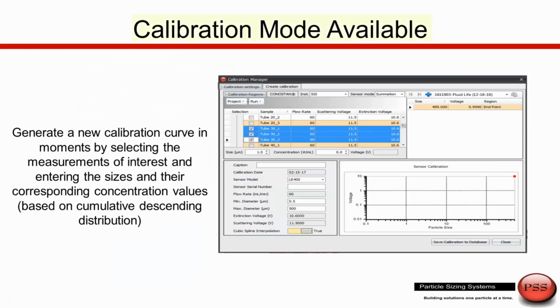Other useful functions in the software include a calibration mode. We certainly can come into the field and calibrate the sensors for customers, but some customers prefer to do this calibration themselves, and we're just showing the calibration mode screen where we can do calibration based on either samples and tubes or just manual measurements, so that we could import the C of A and then make it fairly easy to match the thresholds so that we can calibrate the sensor. And we do this probably every 6 months or annually depending on the protocol in a given customer's lab. So this is just showing the screen for the calibration mode.